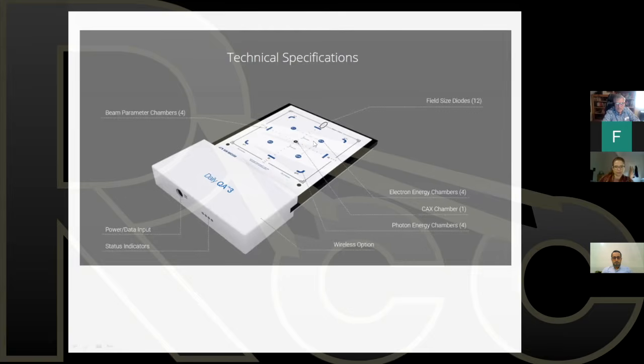Has a chamber right in the center. Has some diodes along the side to detect the field size. This test device gives the therapist an assurance, confidence that the radiation output of the machine is going to be consistent, is actually correct that day. So the therapist will set this device up and go through a protocol which the physicist has set for the therapist. And it has to do with field size. The protocol will also specify what the output of the machine should be in the center for a given number of monitor units, typically 100.